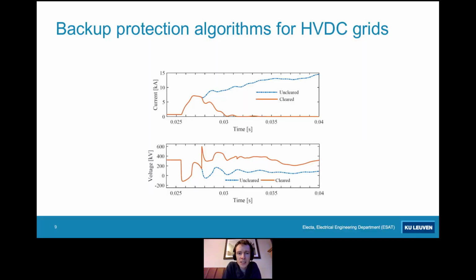Finally, we also needed backup protection algorithms that could determine whether a breaker had operated or not. These graphs show two currents and two voltages. One is for an uncleared fault, so a fault that is not properly interrupted by a breaker, and this is the blue curve. You can see that the blue curve ends up with high currents and low voltages. And the other curve is for a fault where the breaker has acted correctly. So you see that the breaker has driven the fault current to zero and has driven the voltage back up to nominal values.